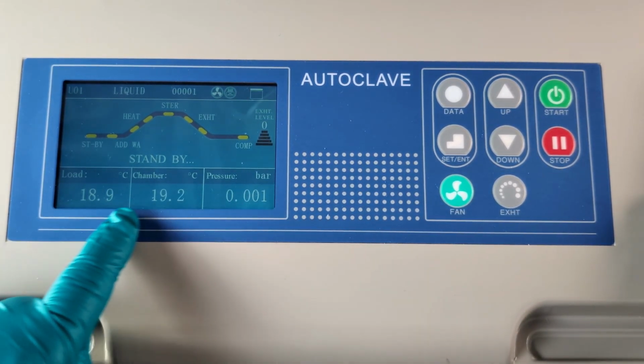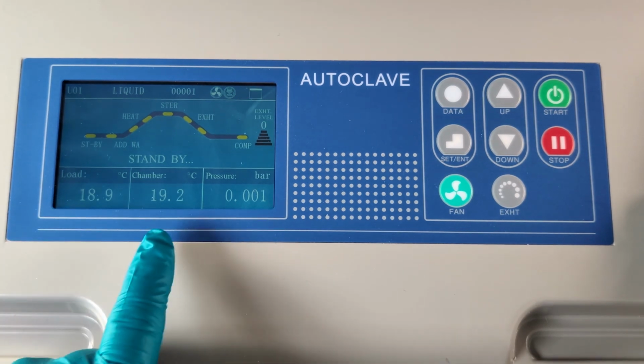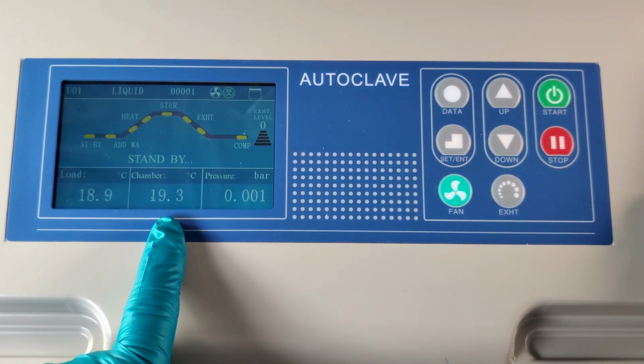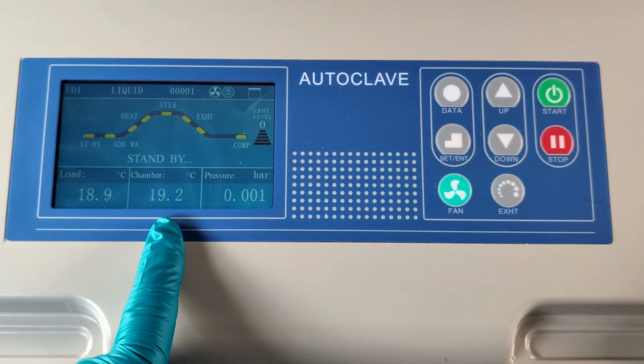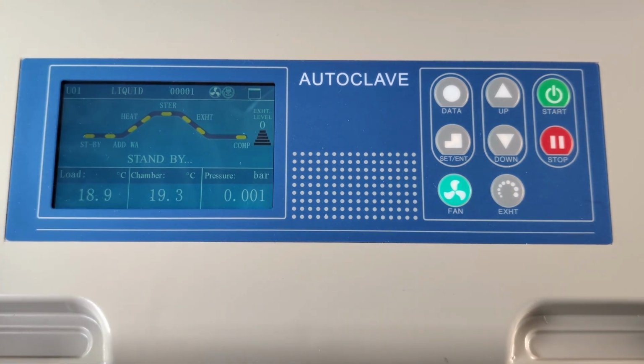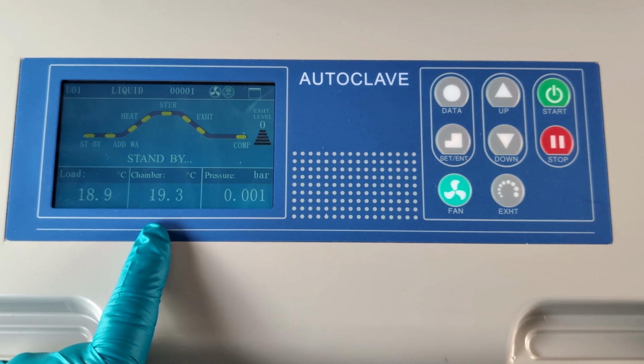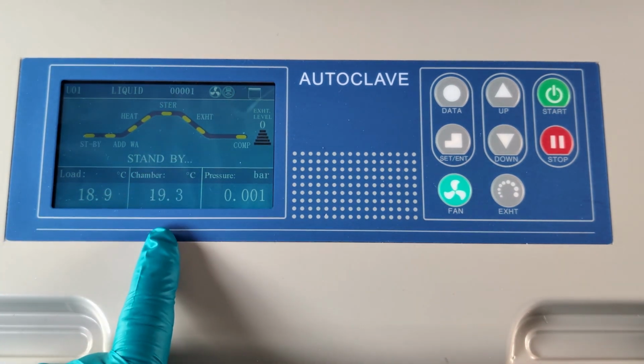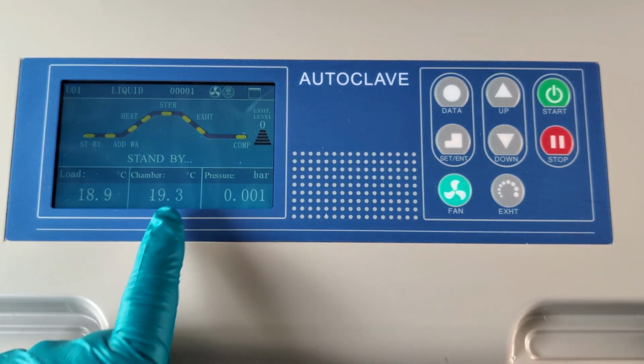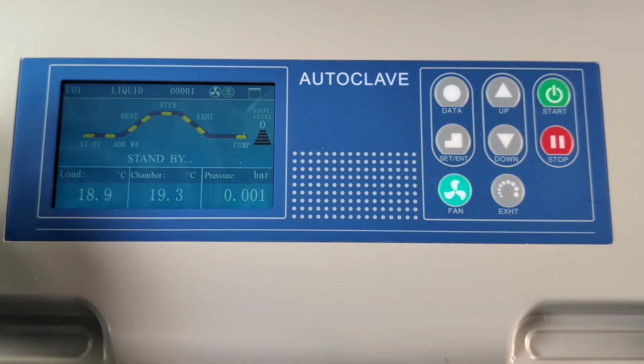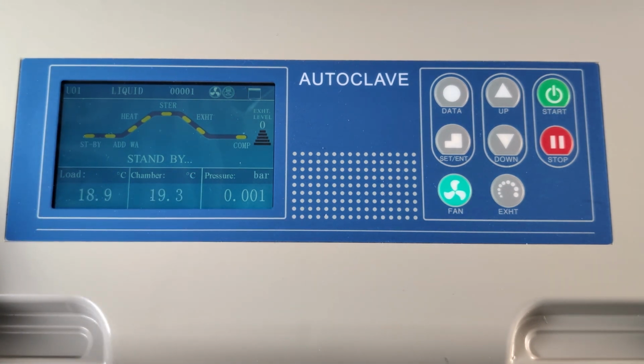Next, we come down to these 3 parameters that you have here. You have the chamber temperature, and that is self-explanatory. It tells you the temperature within the chamber, so you can check that it has actually got to the temperature that you wanted at your sterilization time. You'll see that it's set to degrees centigrade. You can also set it to degrees Fahrenheit if you want.